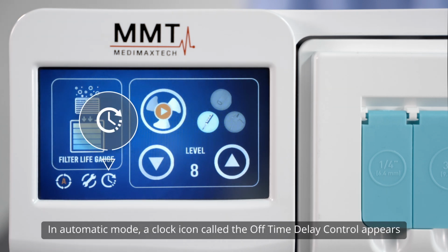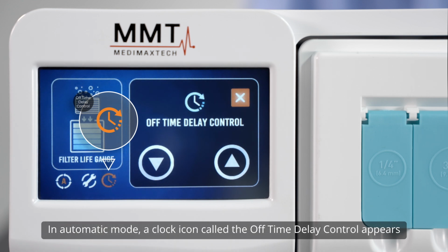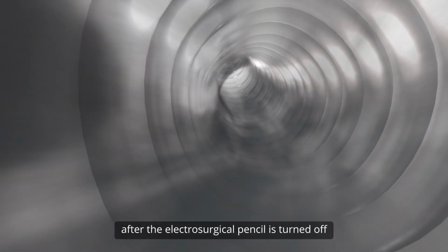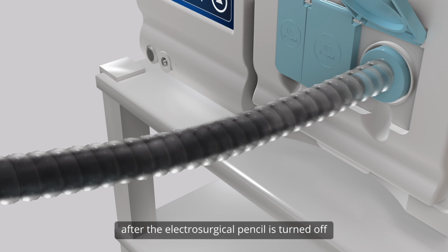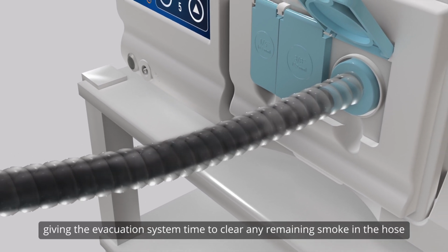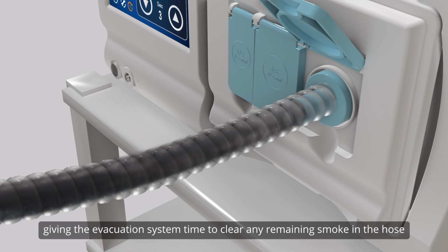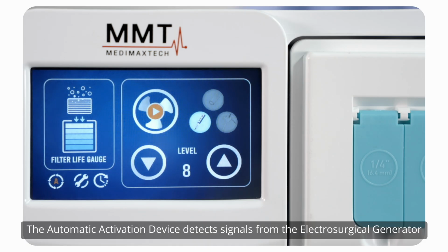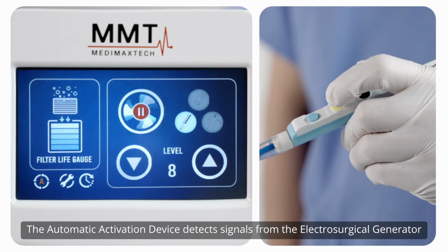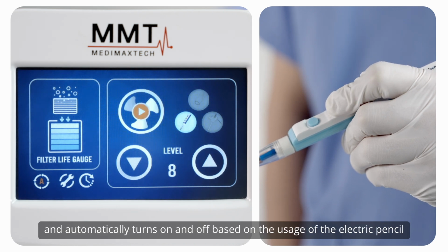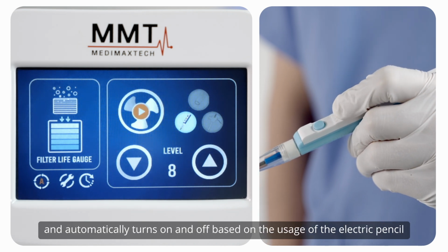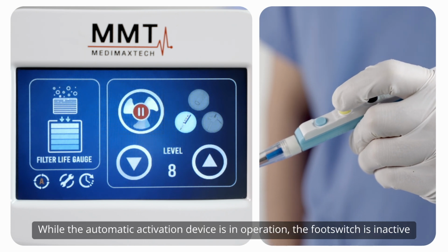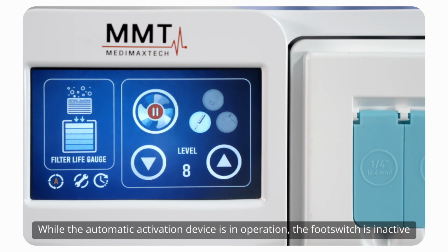In automatic mode, a clock icon called the off time delay control appears, which allows you to extend the device's operation for a few seconds after the electrosurgical pencil is turned off, giving the evacuation system time to clear any remaining smoke in the hose. The automatic activation device detects signals from the electrosurgical generator and automatically turns on and off based on the usage of the electric pencil. While the automatic activation device is in operation, the foot switch is inactive.